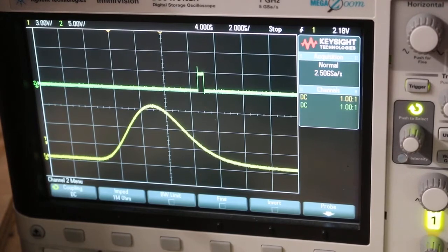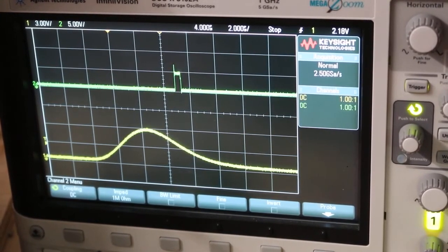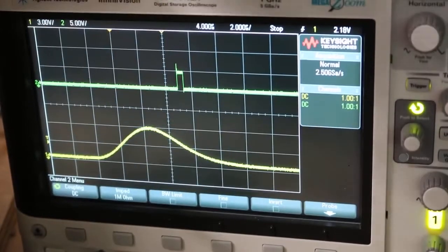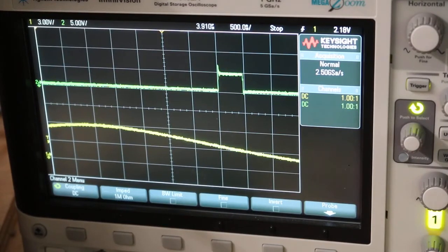But you can see every one of the pulses that's above the internal lower level that I've set on the SCA generates a pulse. And as I said, the oscilloscope on channel 2 is set at about 5 volts per division, so it's a 5 volt pulse. We can nail down the time though. If I move it over just a tad bit, it's a 5 volt pulse lasting about 500 nanoseconds.